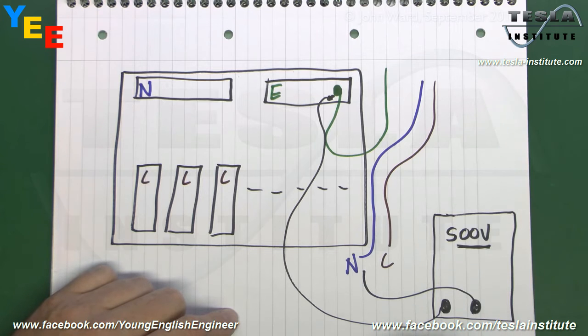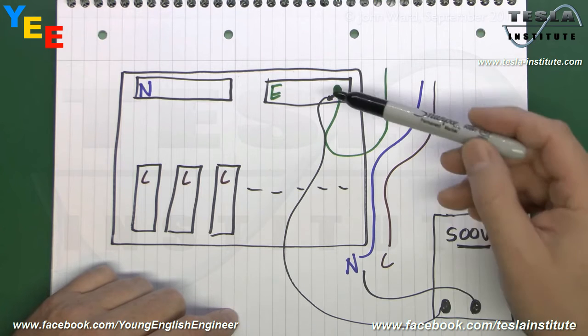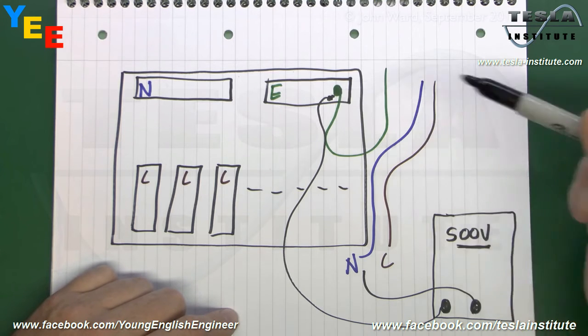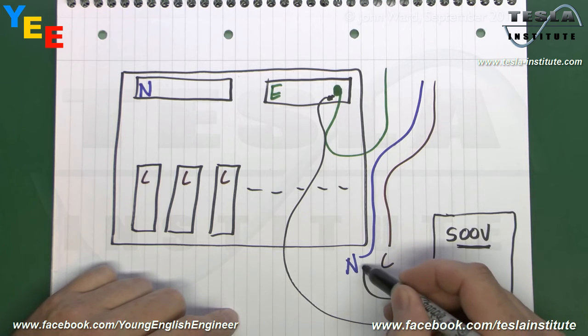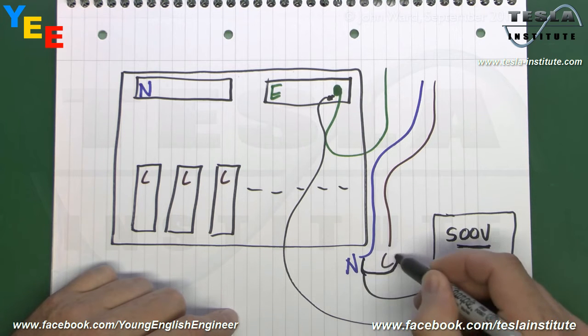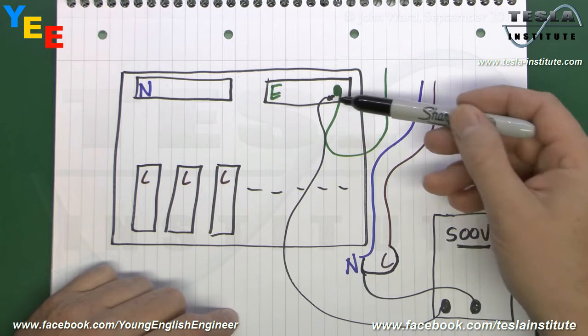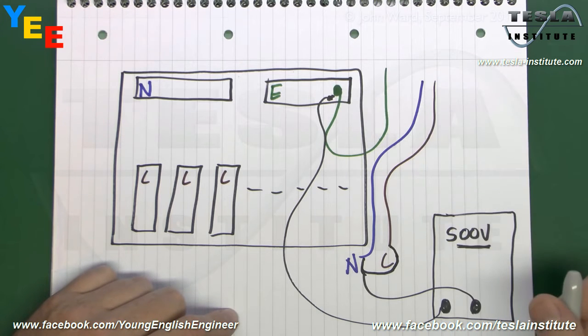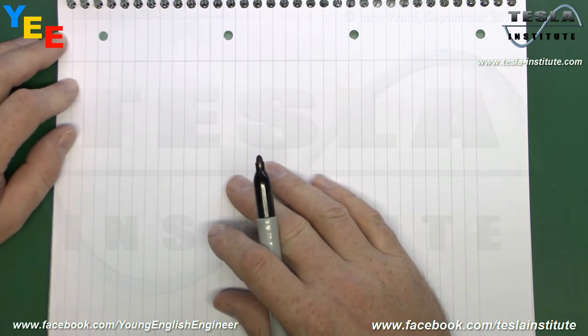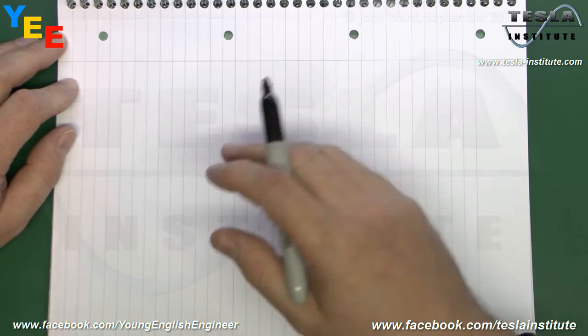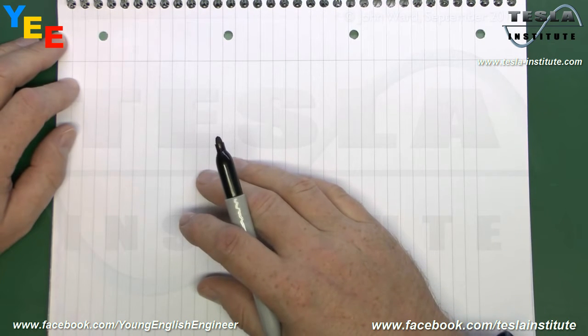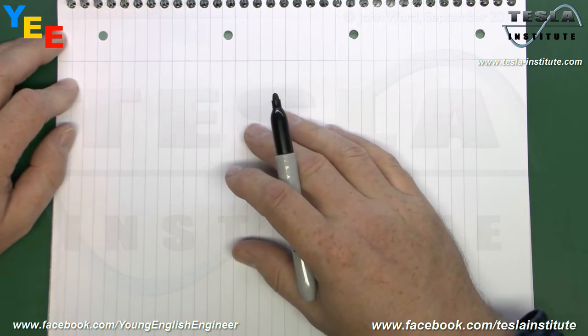However, there is another option, and if there is equipment connected which is either not possible or it's impractical to disconnect, then what you can do is test between the earth connection here and then actually join these two together. So you're basically testing between both those connected together and the earth conductor there. So that's a possible option if there's something connected up there which you either can't get at or simply not practical to remove. Now, say for a new installation, of course, there shouldn't be anything connected in because any kind of socket outlets, for example, wouldn't have any appliances plugged in yet because presumably the building is not actually yet occupied.